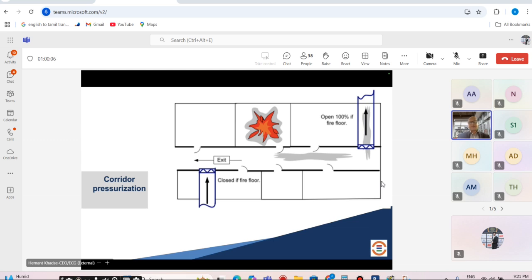When a corridor is pressurized, again, it is a dual responsibility for you to look at your force on the door, that it doesn't exceed 110 newtons, because that's again regulated by codes and standards. At times when you have only single injection pressurization systems, there are high chances that the location where your fan is located, either on the ground floor, which is also the final exit discharge, you will have a lot of dilution of airflow. At the same time, if you are on the top floor as the supply fan for pressurization, you will also expect door openings for egress. So maybe the pressure is less where the door opening is high, or the door is being used as part of egress, and the other floor will have high pressure.